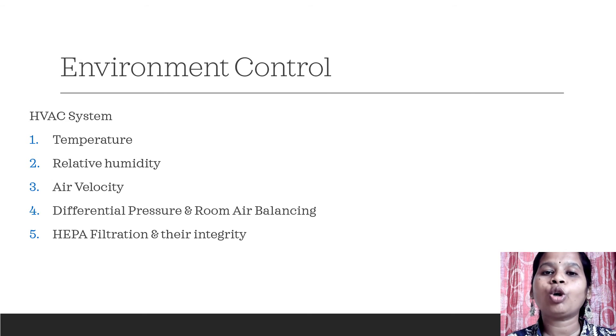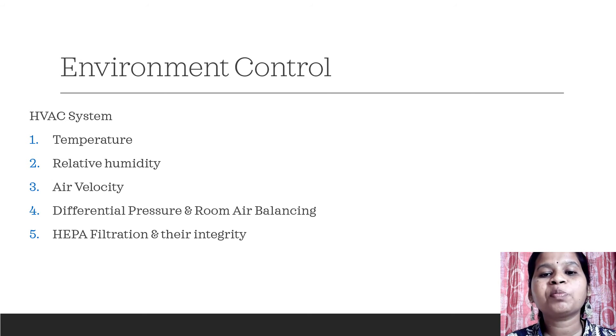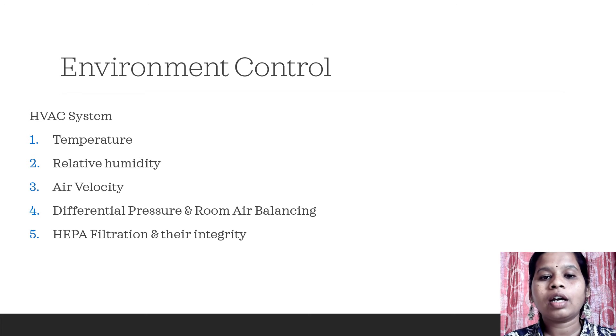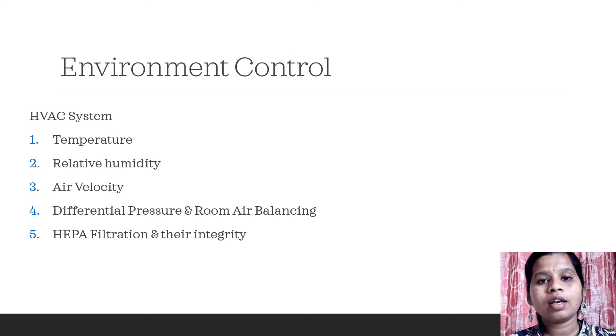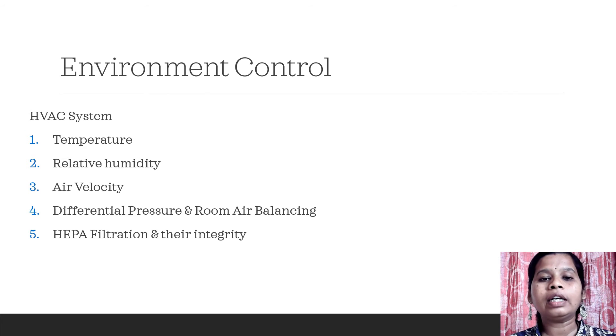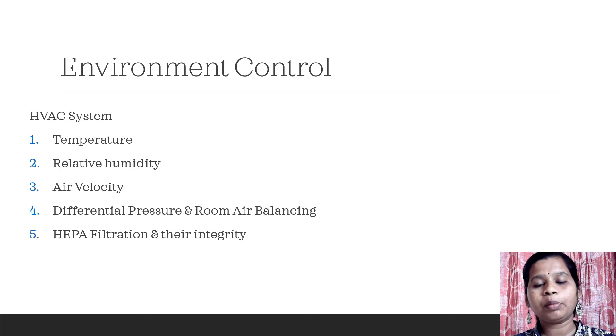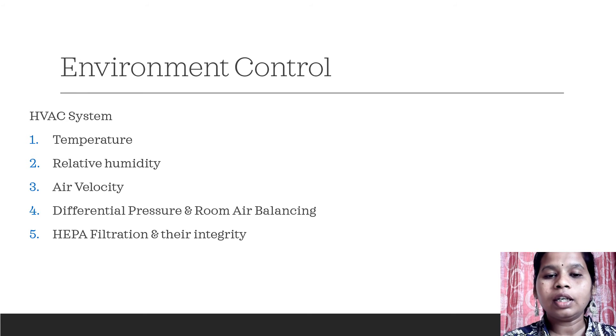Next is HEPA filtration and the integrity of the HEPA filters. Integrity is tested by performing the DOP test or DOS test. The DOP test is the Dispersed Oil Particulate test, and DOS is the Di-Octyl Sebacate particulate testing. Using these two tests, the integrity of the HEPA filters is checked. If the filters are not integral, they will be discarded or repaired as per the need.